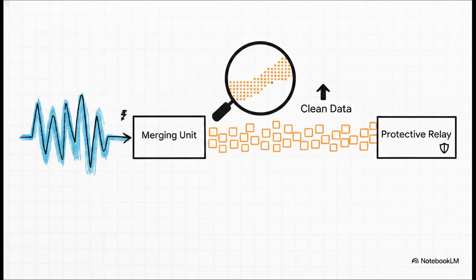bus. The advantage of these merging units is pretty staggering. Instead of analog wires carrying dangerous voltages into the control house, the MU publishes universal datasets: voltage, current, breaker status, the whole shebang. For standard protection, the base sampling rate is an incredible 80 samples per power system cycle. For high-frequency applications, like power quality, it's hitting 256 samples per cycle. The relays simply subscribe to this clean, perfectly aligned digital data, getting a flawless, saturation-free picture of the fault.